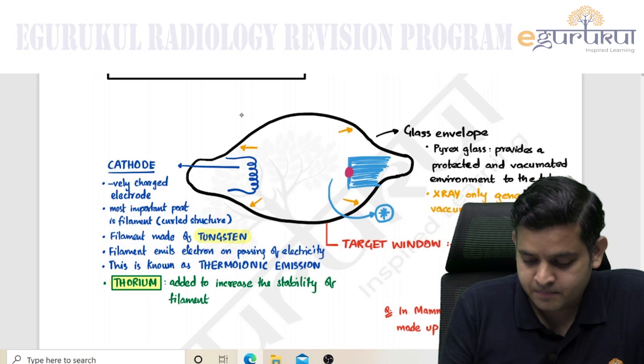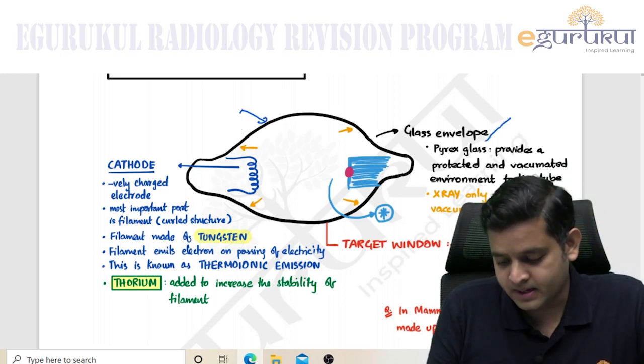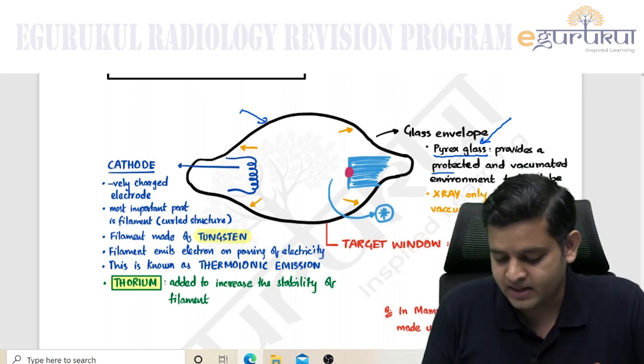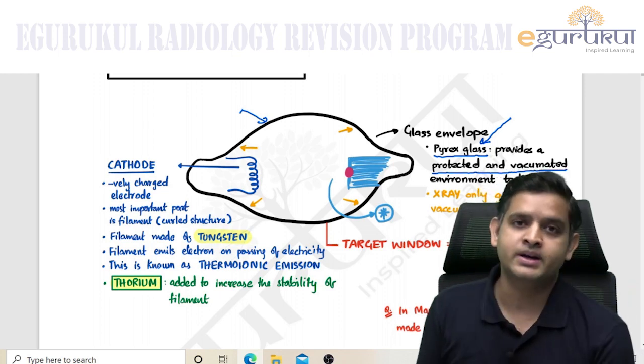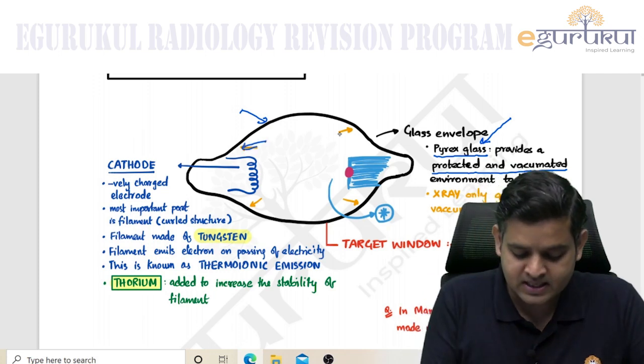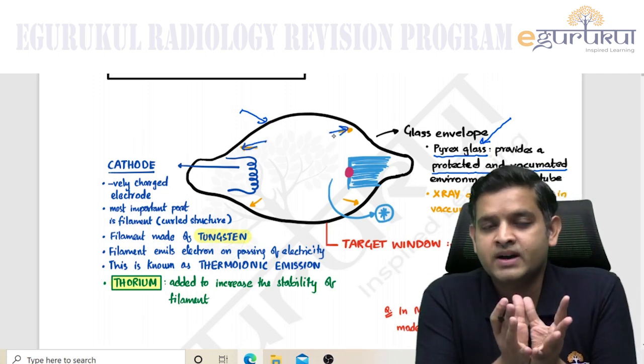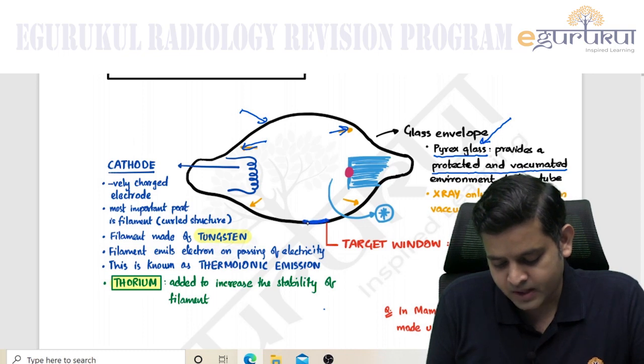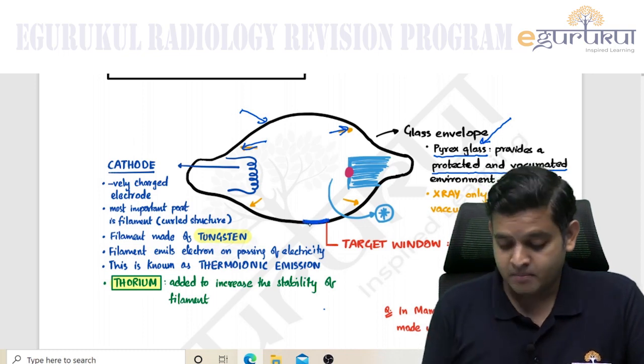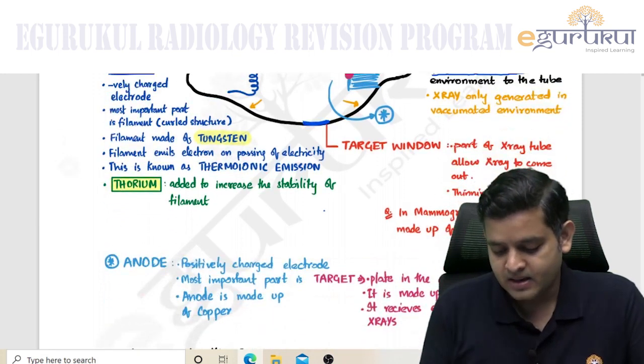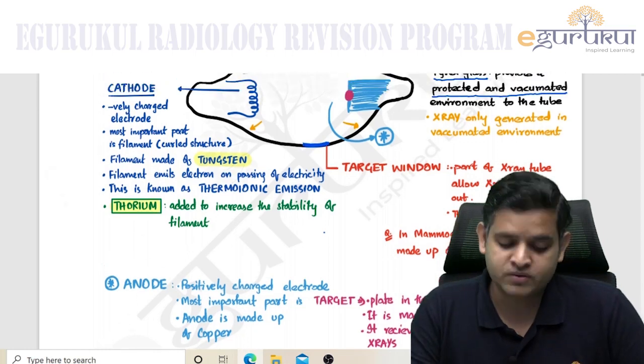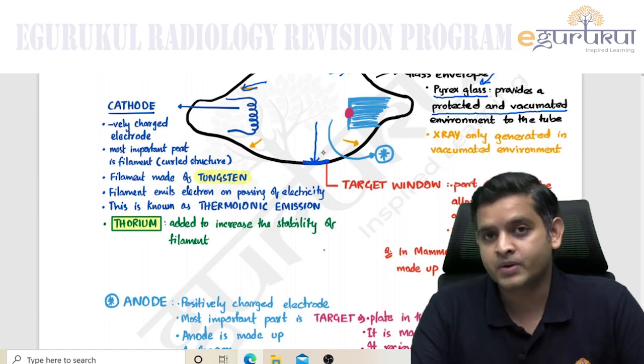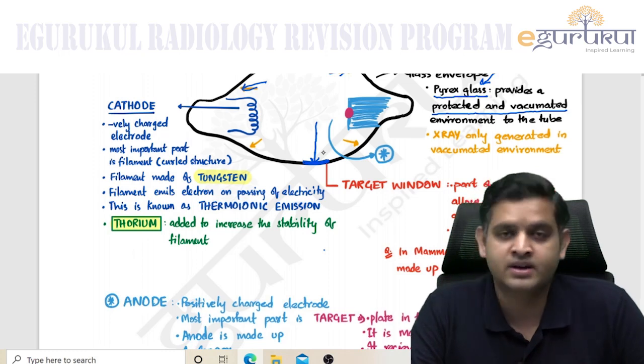Looking at the glass envelope, please remember it is made up of pyrex glass. The purpose is to provide a protected and vacuumated environment to the tube. It provides a protected environment so that x-rays do not escape, and a vacuumated environment so that x-rays can be generated. There is a window in the lower part of the envelope, which is nothing but the thinning of glass, allowing x-rays to come out of that particular part.